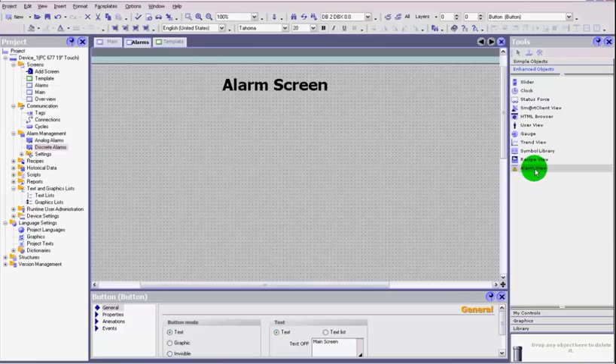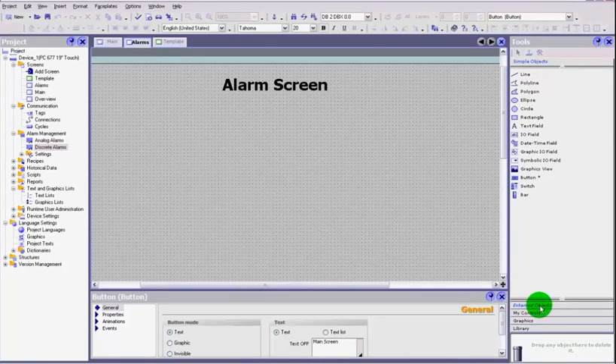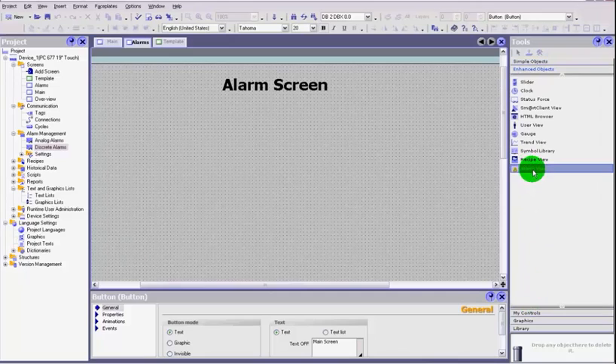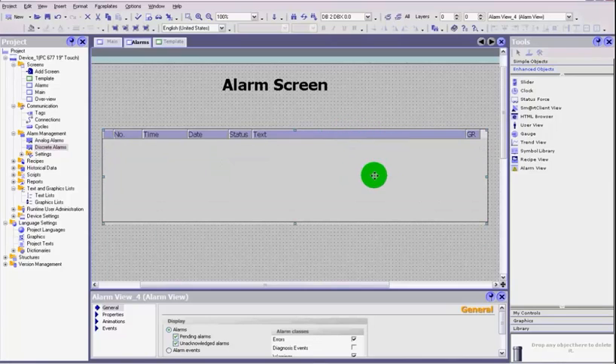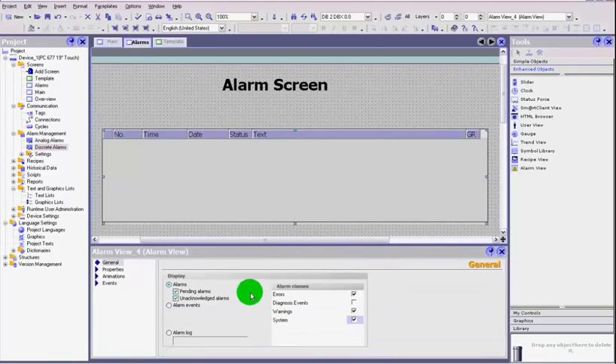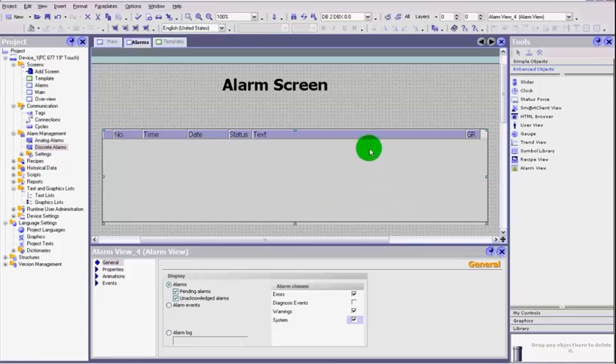Go to your alarm page. We need to create something to display those alarms. Go from simple objects into enhanced objects — you'll see alarm view. Click on that, drag and drop it into our page, and we get a screen to show our alarms. In the properties you can see alarm events, pending alarms, acknowledged alarms, and unacknowledged alarms. You set up the classes of what you want this object to show.